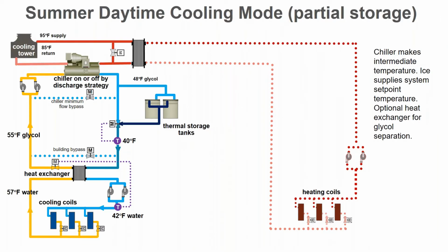In the summertime, you've kind of seen the mode often. Now we are going to use the chiller. This is what would be called partial storage. If you had a 2,000-ton building and you had a 1,000-ton chiller, maybe 1,000 tons is coming from the chiller at this point, and you could get another 1,000 from the storage. So the storage is doing part of the load, hence the name partial storage.